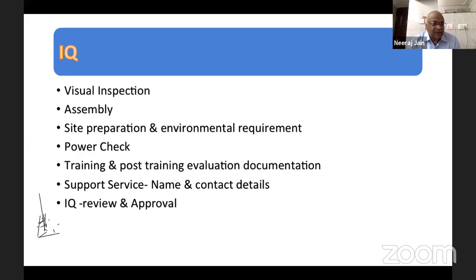Now, you're installing your machine. On opening the box, do a visual inspection. You have ordered a new machine. It is actually new, it is not refurbished, it is not damaged. Then see the assembly, what all parts there are, when they are joining, how they are joining. You have already checked the site and environmental requirements like temperature, cleanliness, not excess heat, not excess dust, and that sterility is being maintained. Power check: there is uninterrupted uniform power supply, and earthing is proper.